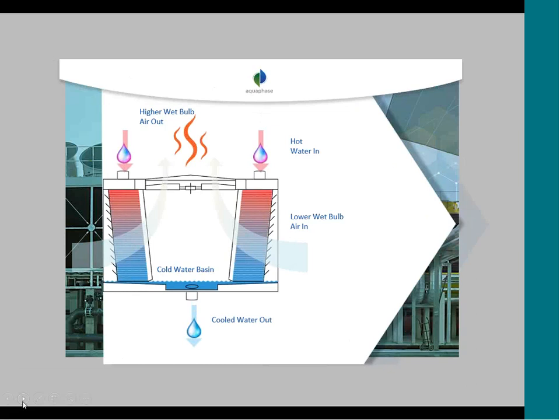Evaporation is the change of state from a liquid to a gas. This change of state requires a lot of energy, and that energy comes from heat—the heat we picked up at the heat load, transferred all the way up to the cooling tower, which we release to the atmosphere through evaporation.